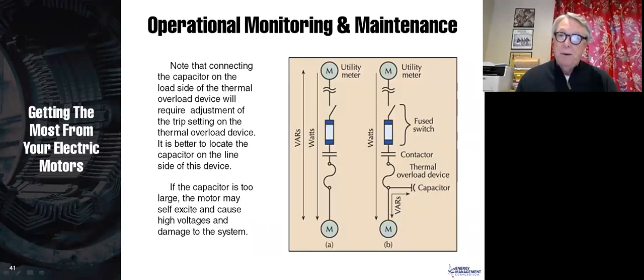Now, if you put a capacitor on the motor, you are supposed to adjust your overload, because when you put the capacitor on the motor, the current in the overload becomes lower than if the capacitor weren't there, and so the motor can get overloaded. You're measuring the current back here and thinking that's the current into the motor, but it isn't. The current into the motor is higher because of this capacitor.